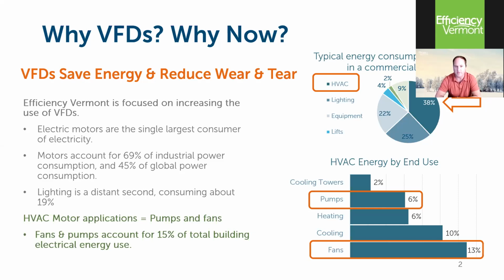If you trim off a few hertz from the top end of a pump or a fan, you can pick up cubic savings, and that's really valuable to Efficiency Vermont as well as to the grid. One of the other reasons we are so excited about motor controls: motors account for 69% of industrial power consumption, 45% of global power consumption. Motors are everywhere.